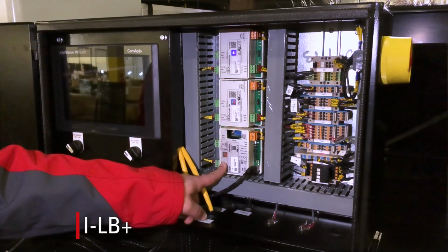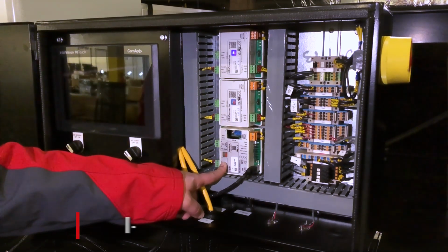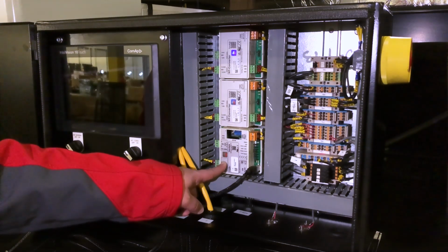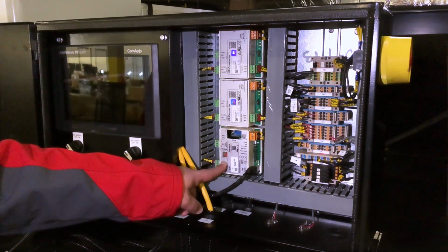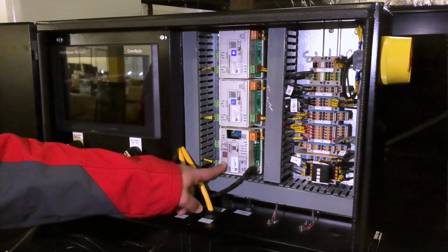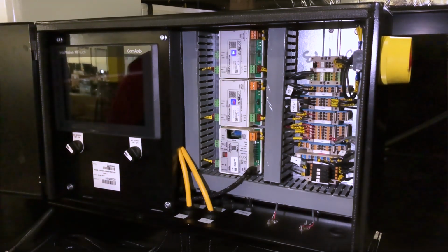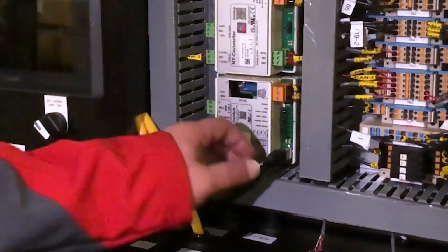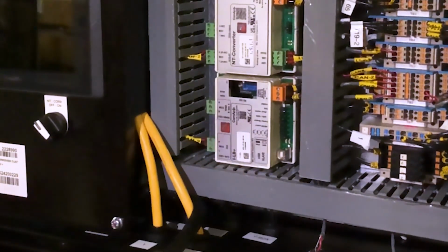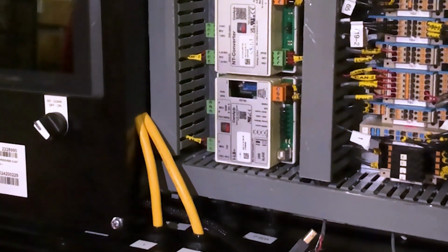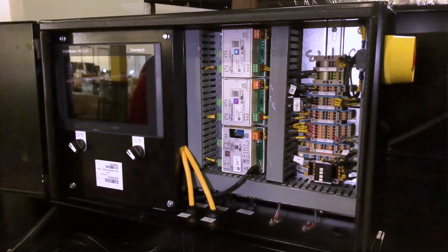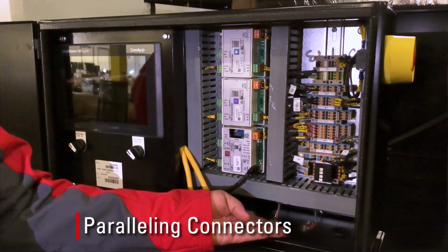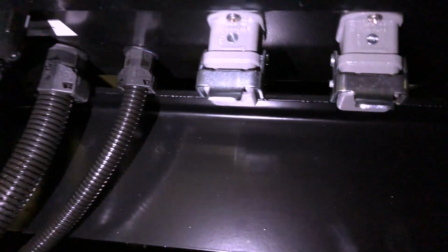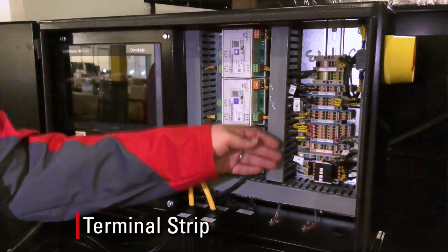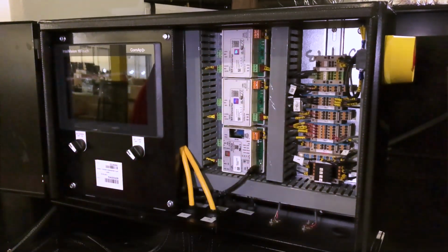Then we have our ILB Plus. This is used to connect to the gensets from ground level, as well as the IV10 touch display. If you need to connect to more than one of the generator controllers to make a set point change, you should unplug the USB connection which goes to the IV10 touch, and then plug your laptop cord into that location. Some other features of the panel include our paralleling connection, which allows you to connect to other units on the paralleling chain, as well as our terminal strip that includes our fuses for the centralized control panel.